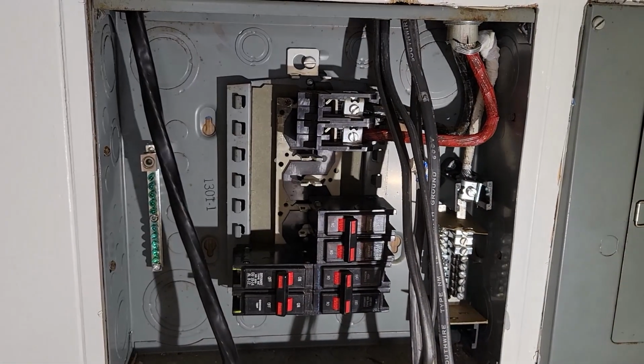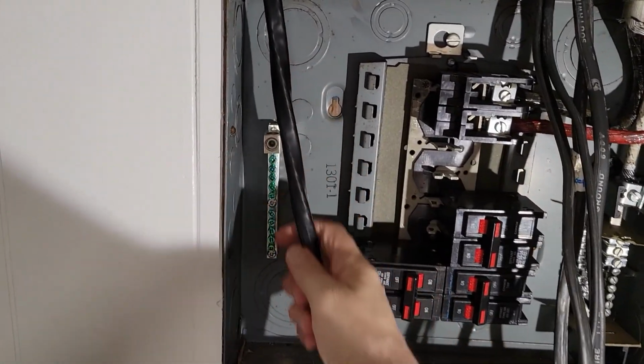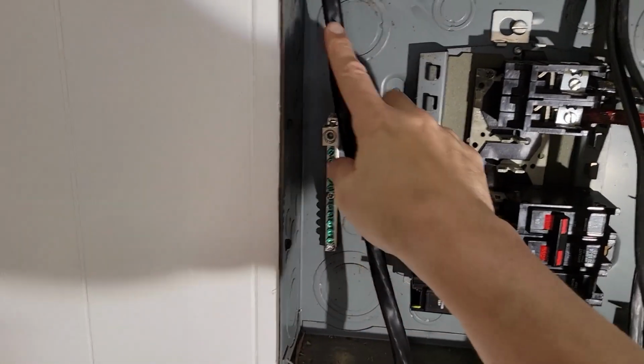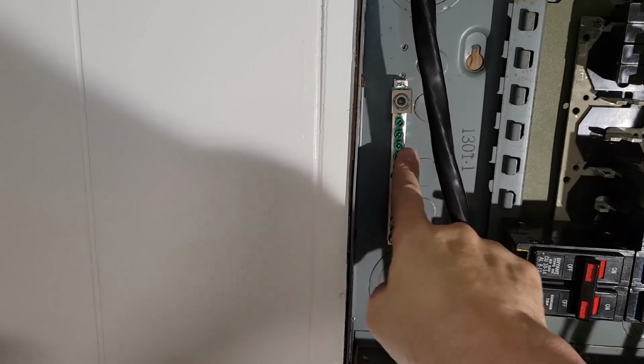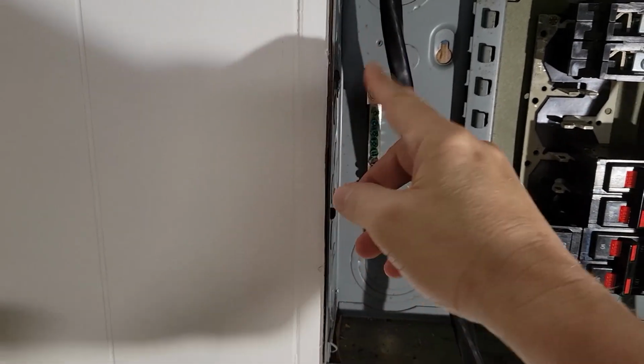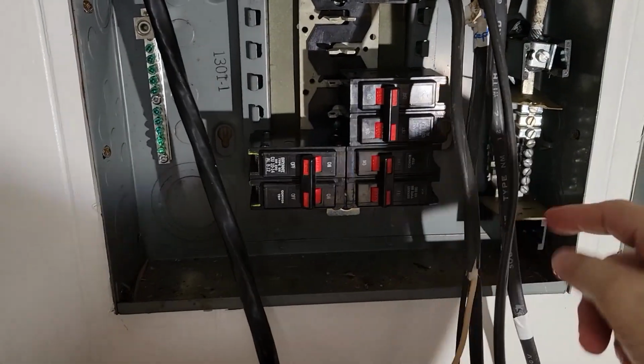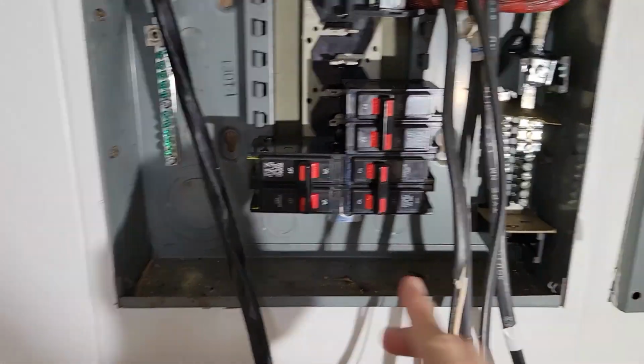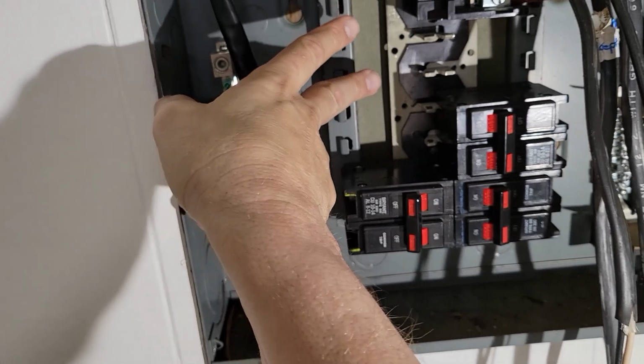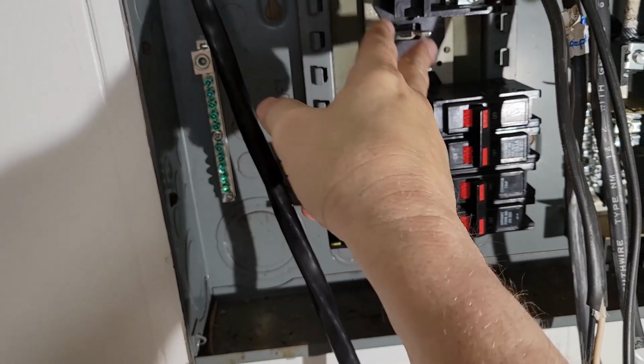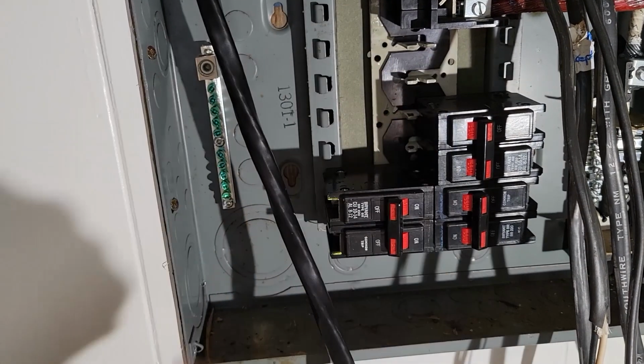With our neutral bar secured, now it's time to deal with our EV cable. What I'm going to do is cut the sheathing off this cable so I can run the ground to here. And then I'm going to bring the neutral over to this side. There's a red and black, and I'm going to put a 50 amp circuit breaker here and tie into that.